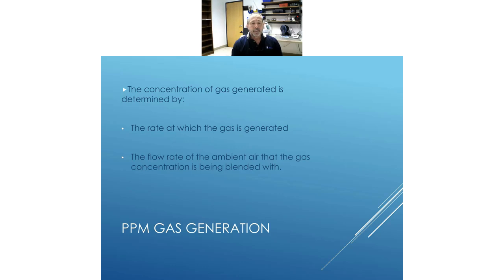The ppm gas generation is determined by the rate at which the gas is generated and the flow rate that it's blended with. Parts per million is a unitless number like percent, so 1 penny in 100 is 1%, and 1 penny in a million is 1 part per million. So we're talking about very small amounts, but these are toxic enough gases that that's all you want. You just want parts per million to calibrate your sensor. The sensor is an early warning device to tell people you need to leave this area. There's beginning to be enough gas present that it could get dangerous.